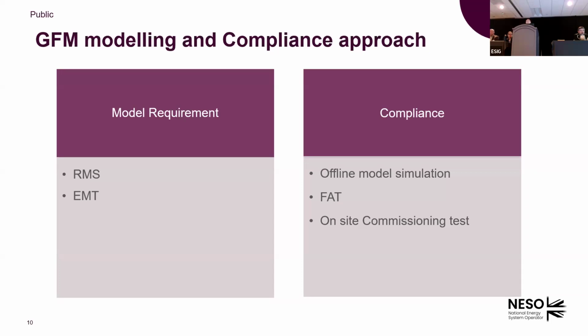So we're putting a lot of emphasis on the factory acceptance test. The vendors have to put the inverter into a test rig and simulate different system events, like a ROCOF event, or a forced oscillation, and see what the response of the inverter looks like. We use that information to validate the EMT model that the vendor provides to the system operator. Then we do a lot of simulations to make sure the whole plant's performance aligns with the factory acceptance tests. The commissioning test itself is fairly similar to the grid following one, because it's hard to create a system event.